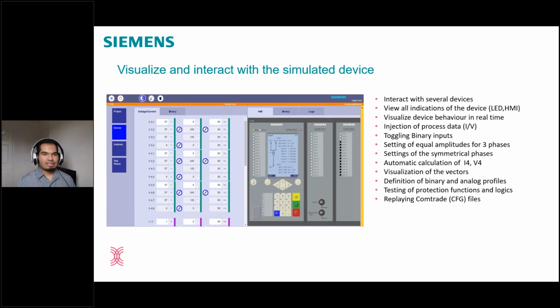And through all these external sources in the digital twin itself, you are able to test the protection functions and logics being the CFC logics, PLC logics, which we have in the relay. And finally, we are able to replay COMTRADE files. So CFG files, whenever a fault occurs at site, you will get a COMTRADE file. You can load the COMTRADE file in the cloud as well and replay it on the same relay and see how the relay behaves, make the changes, and figure out whether that solves your issue or not. So this is just a high level overview on what the digital twin can do.